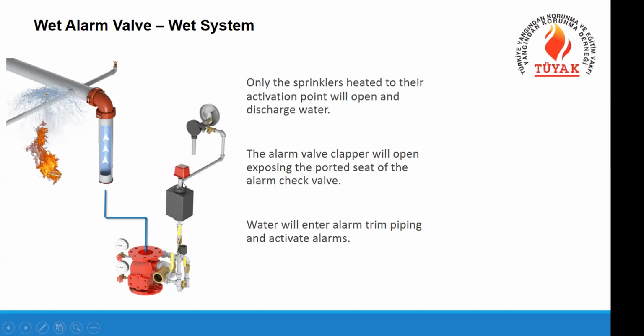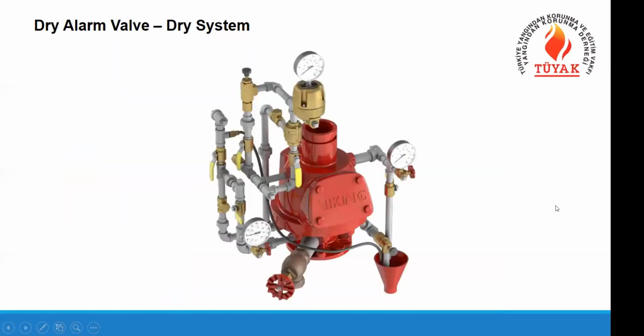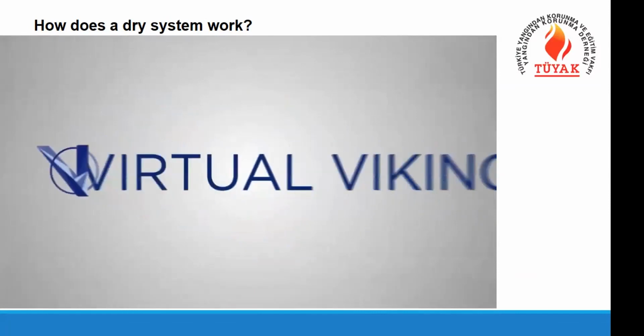So also we have here an electrical alarm device. When water comes here, the electrical alarm is given to the fire detection panel, and it gives that signal as an alarm, as a secondary electrical alarm. Another application is the dry systems, and we use dry alarm valves in these kinds of applications, and it looks more complicated. So again, I will show you an animation of how it works and where it is used.